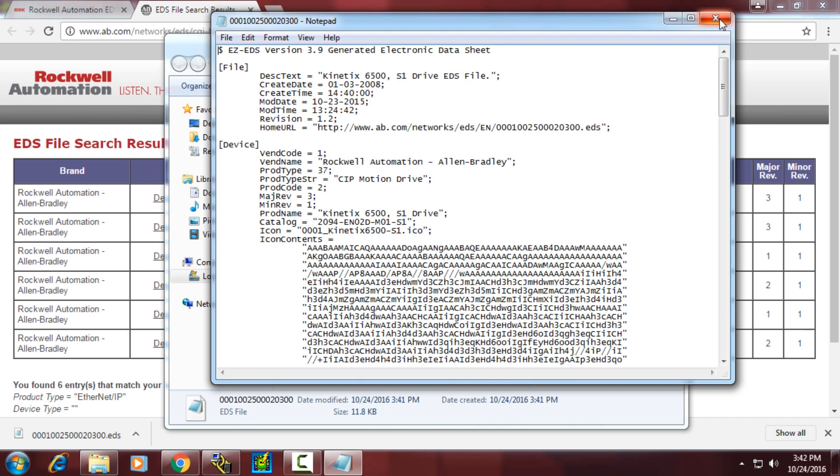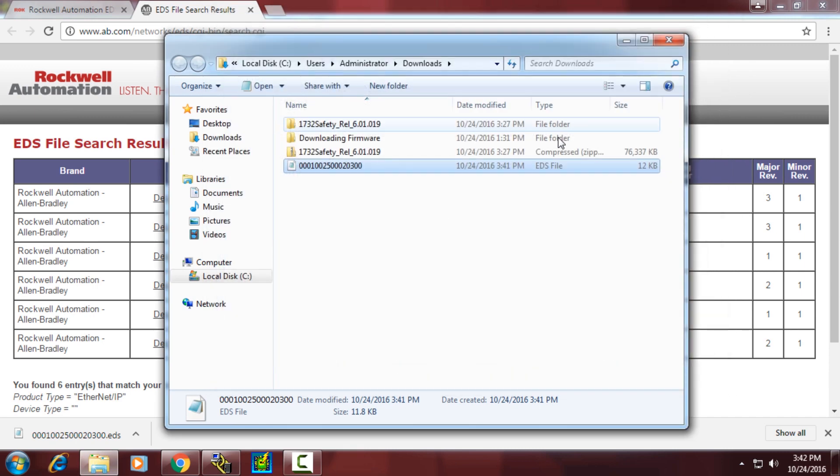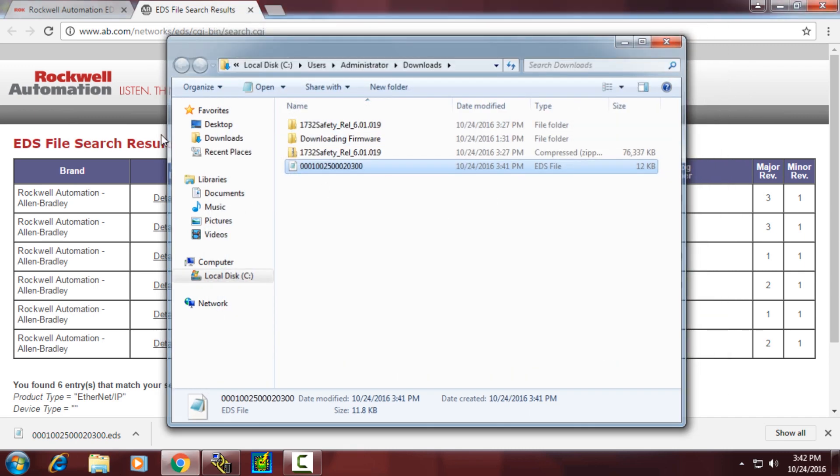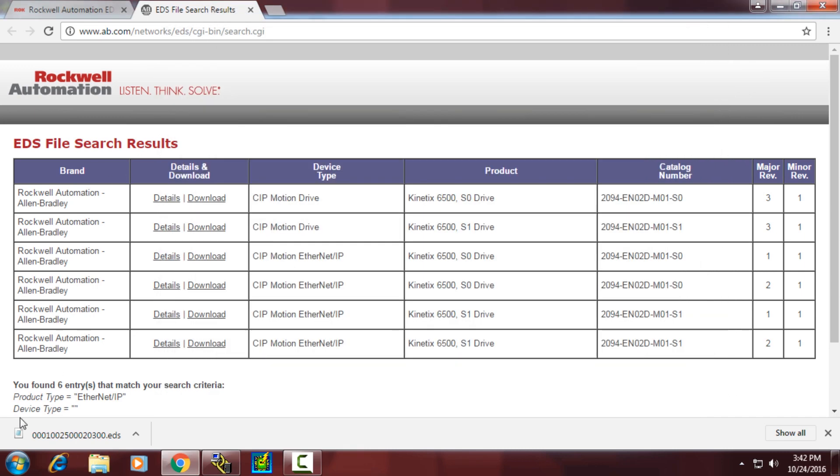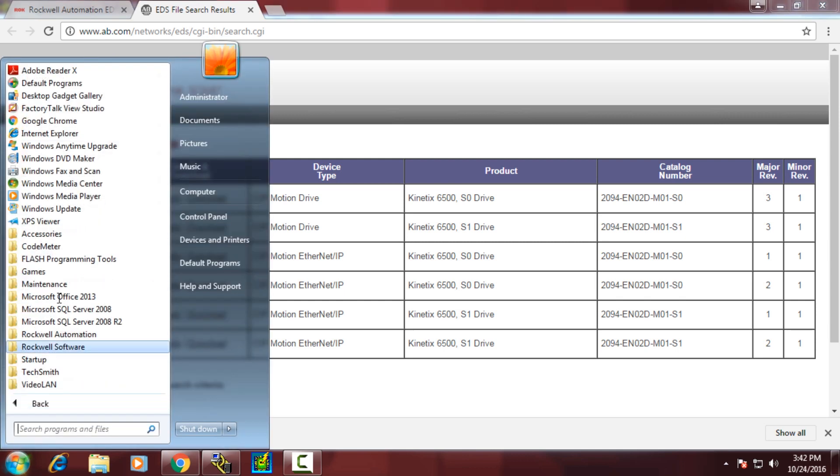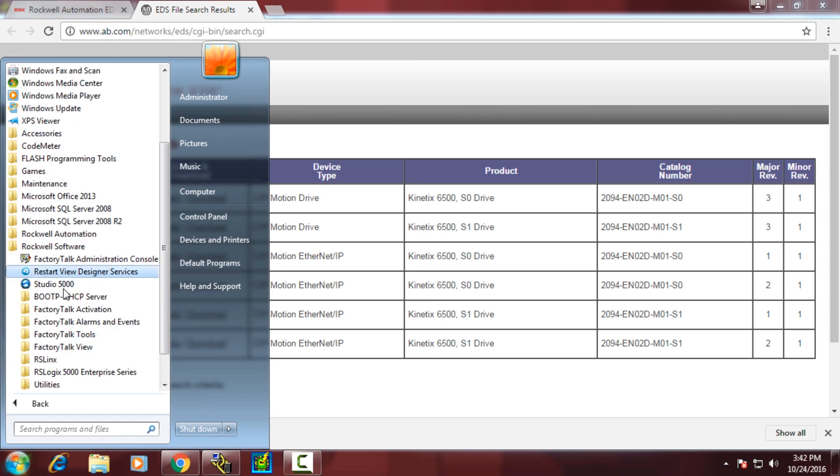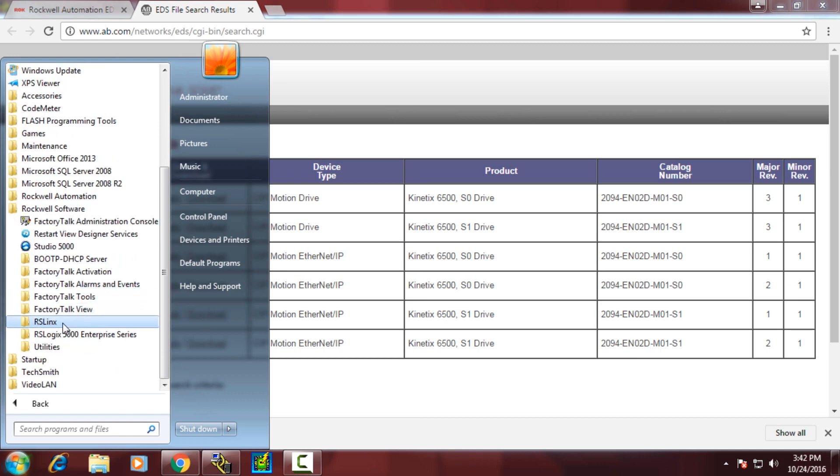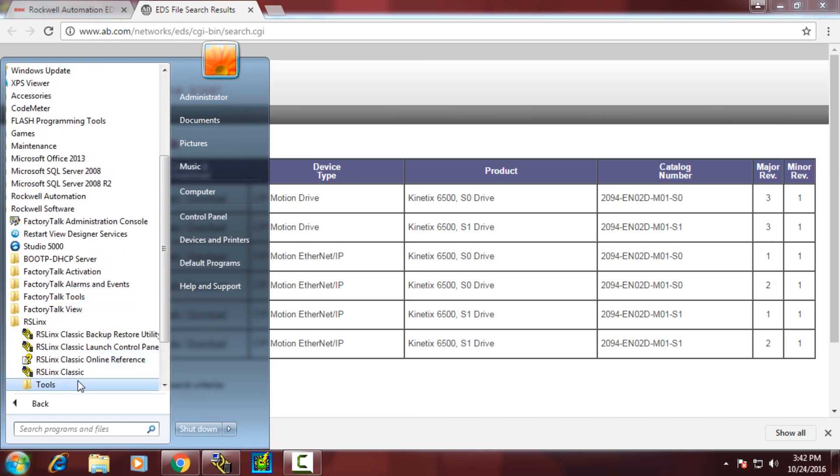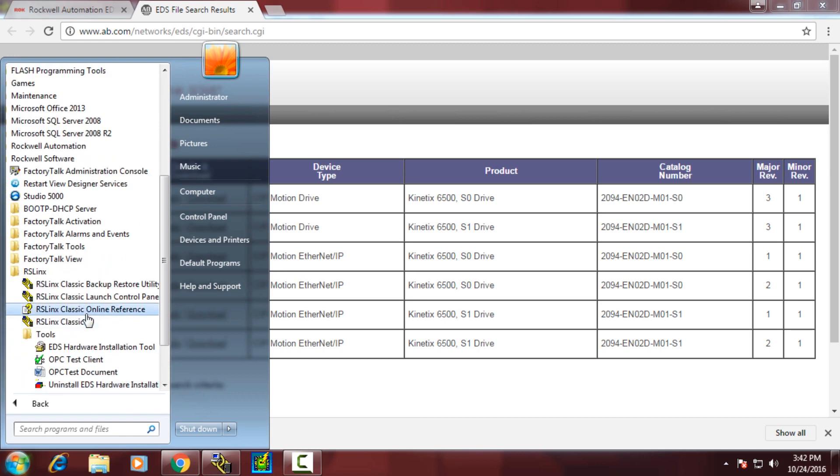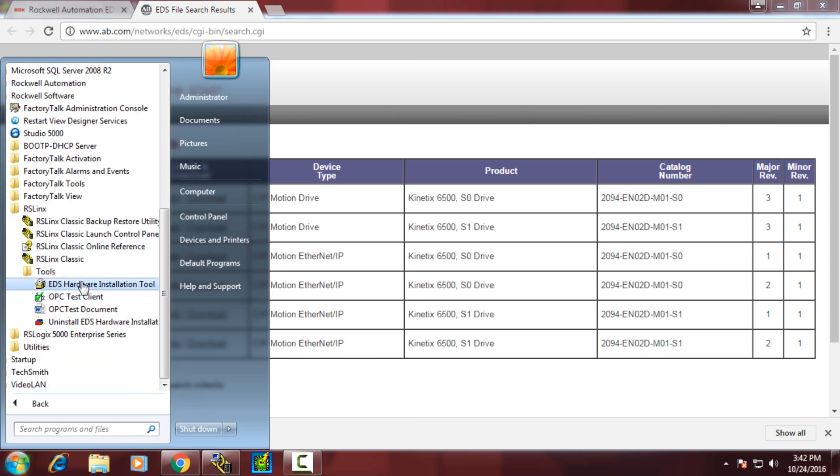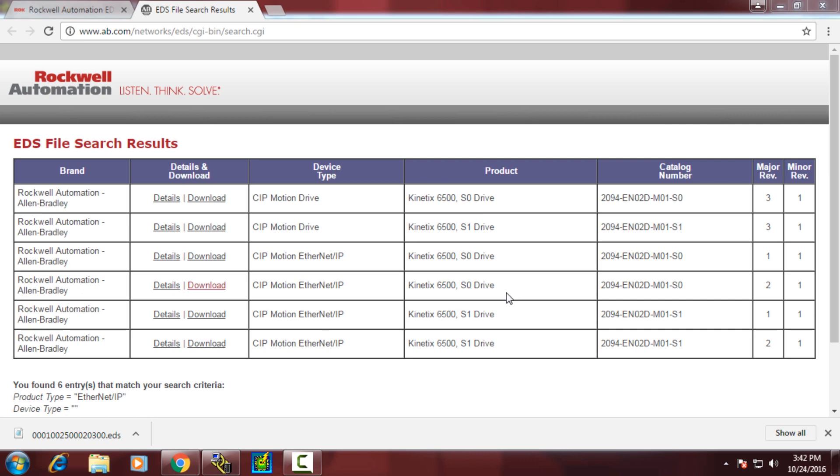In order to install an EDS file, we'll need to use a separate tool. You'll find that tool under Start, All Programs, Rockwell Software, RSLinx, Tools, EDS Hardware Installation Tool.